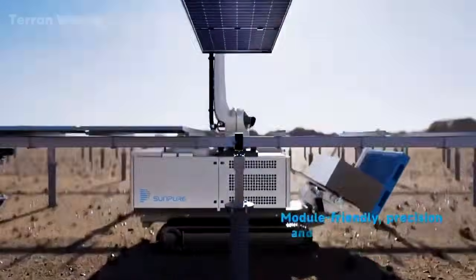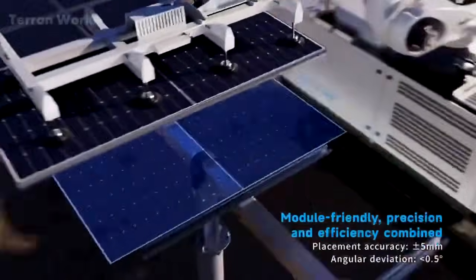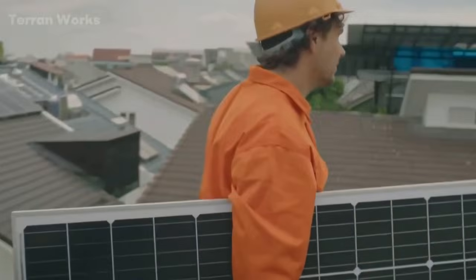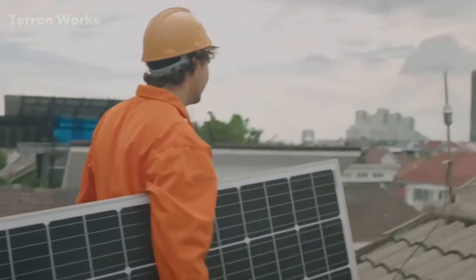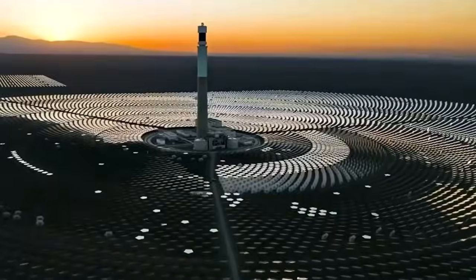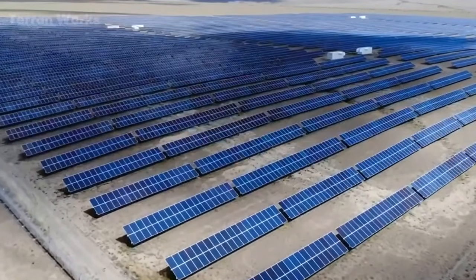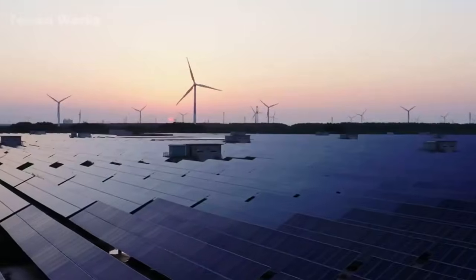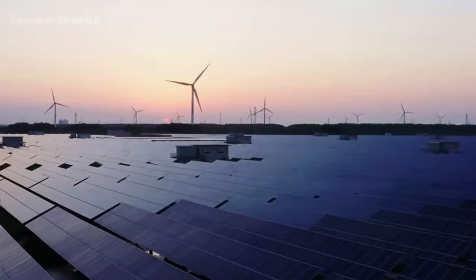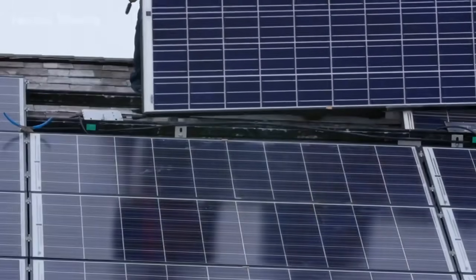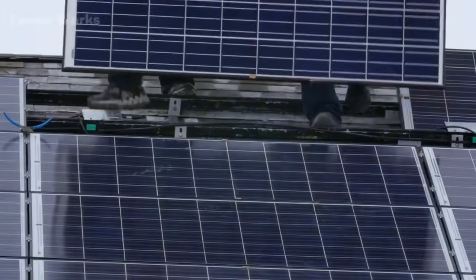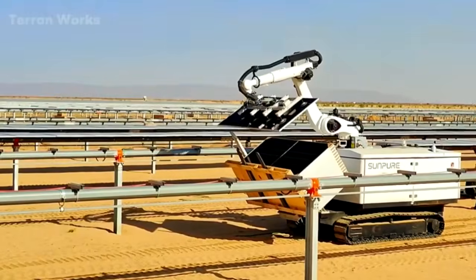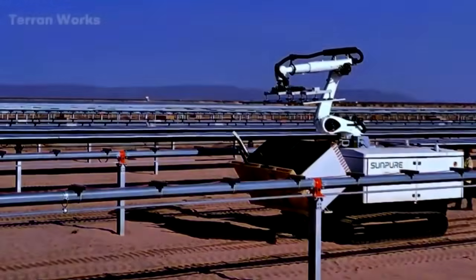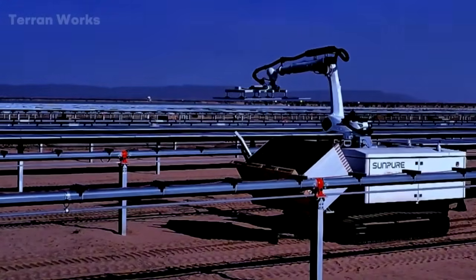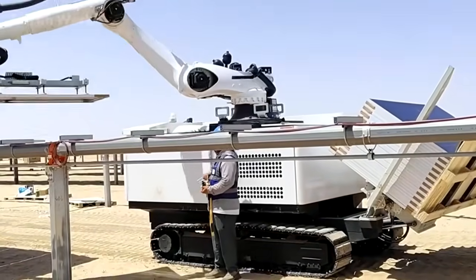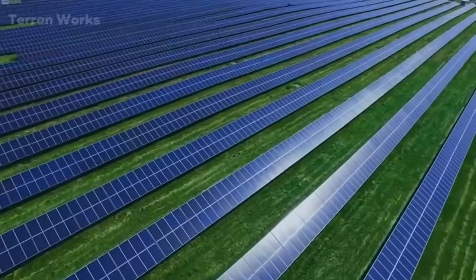After crews align steel rows across the desert, they load them with 400 to 600 watt panels, one module at a time. The weak point is not the glass, it is the fastening. Aluminum clamps grip the module frame, and specialized bolts lock it to the rail. No loose edge. Modern modules usually use tempered glass and aluminum frames because desert sites bring abrasive dust and wide day-night temperature swings. That choice limits flexing, edge damage, and surface wear, but installation still decides reliability. Each panel must sit square, tight, and electrically safe.